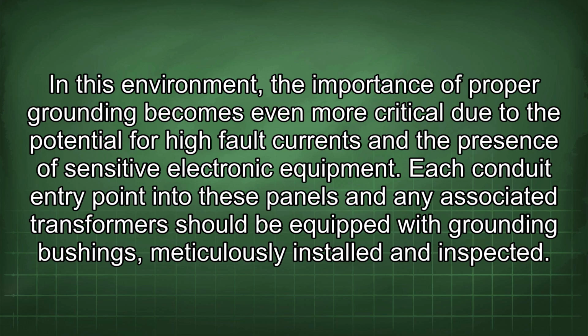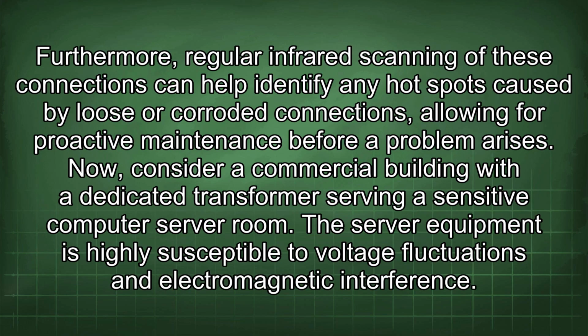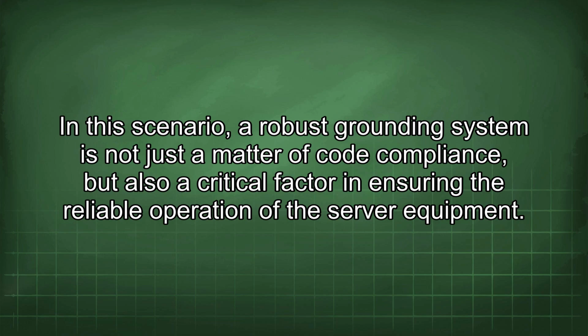Each conduit entry point into these panels and any associated transformers should be equipped with grounding bushings meticulously installed and inspected. Furthermore, regular infrared scanning of these connections can help identify any hotspots caused by loose or corroded connections, allowing for proactive maintenance before a problem arises. Now, consider a commercial building with a dedicated transformer serving a sensitive computer server room. The server equipment is highly susceptible to voltage fluctuations and electromagnetic interference. In this scenario, a robust grounding system is not just a matter of code compliance, but also a critical factor in ensuring the reliable operation of the server equipment.